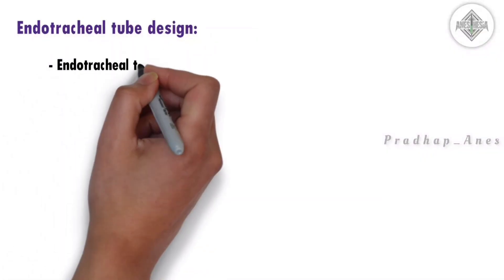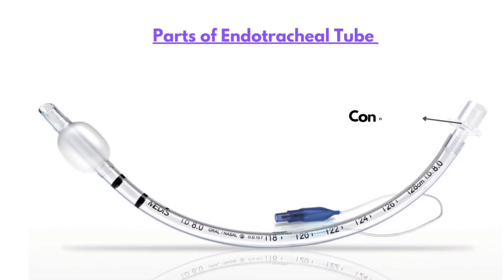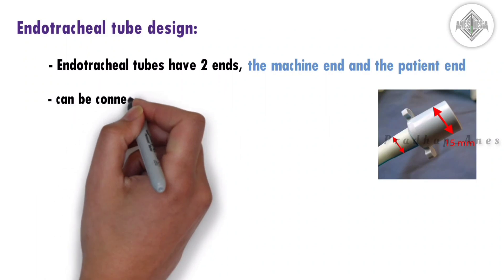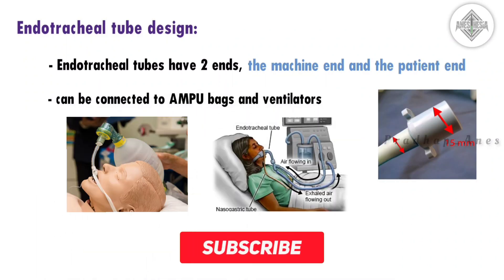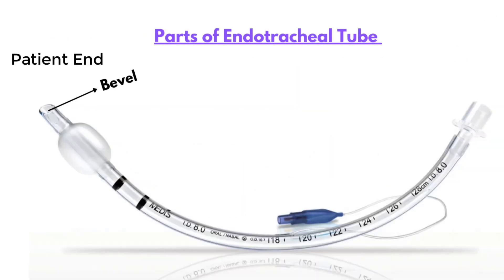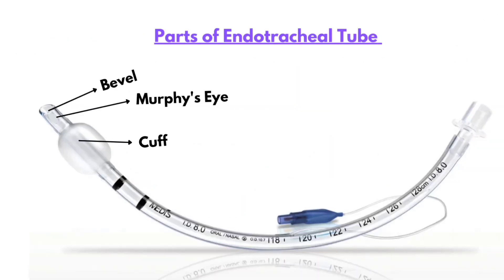Endotracheal tube design. Endotracheal tubes have two ends: the machine end and the patient end. It has a universal 15 mm connector that can be connected to AMBU bags and ventilators. Then there's a transparent curved tube. At the patient end we have a cuff and bevel with Murphy's eye.